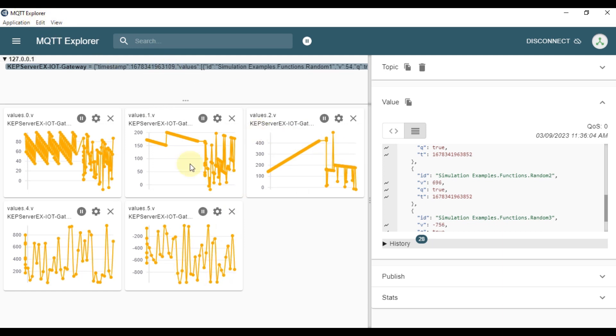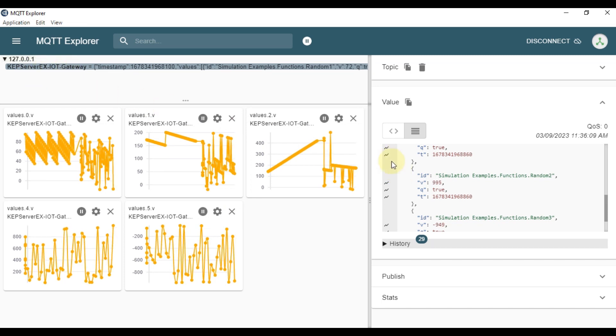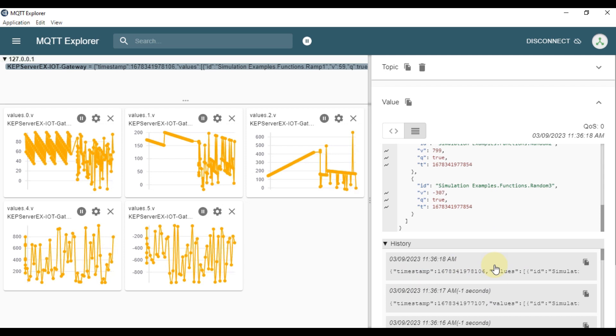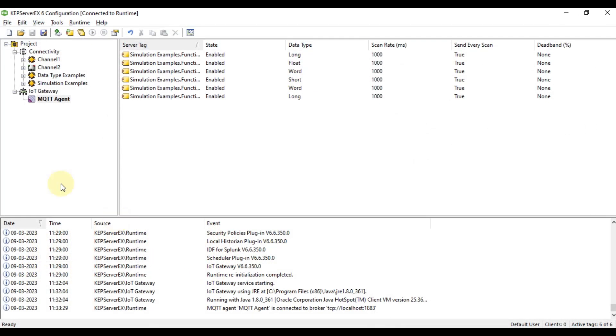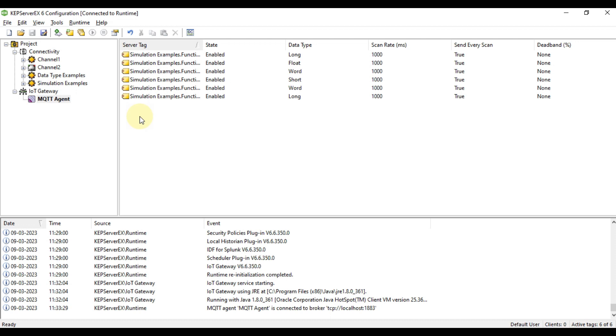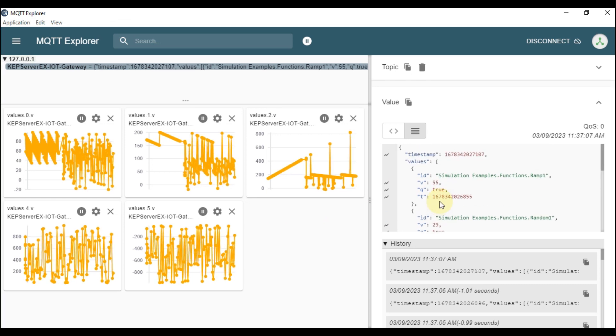MQTT Explorer is acting as the MQTT client, subscribing to the topic and reading values from JSON format — you can see the history and last update time. This is how you use the MQTT agent IoT gateway in KEPServerEX. In a real-world scenario, if KEPServerEX is installed in the field and you want to send data over MQTT to a SCADA system or enterprise system, you can use the KEPServerEX IoT gateway MQTT agent. On the client or enterprise side, extract data from the JSON format.